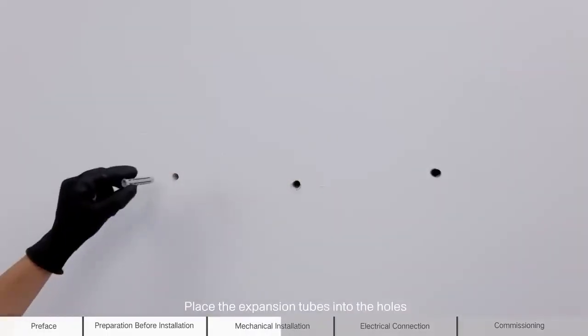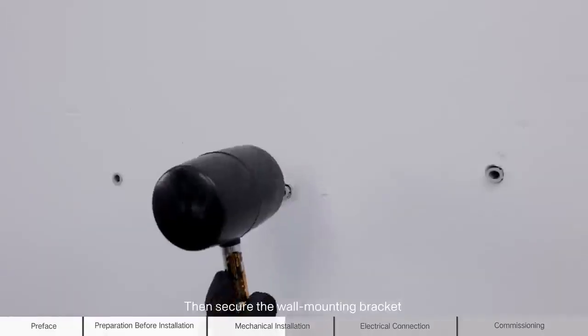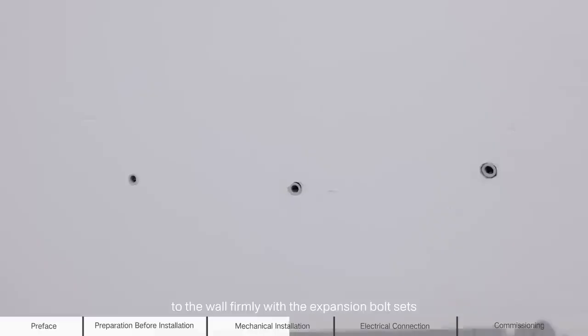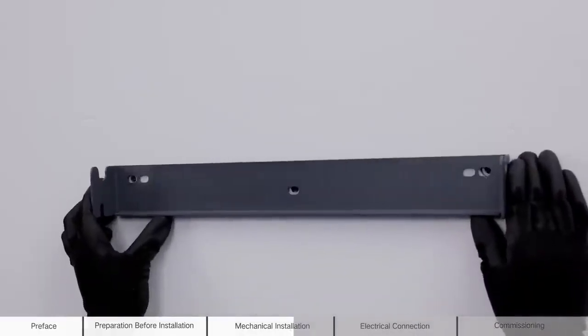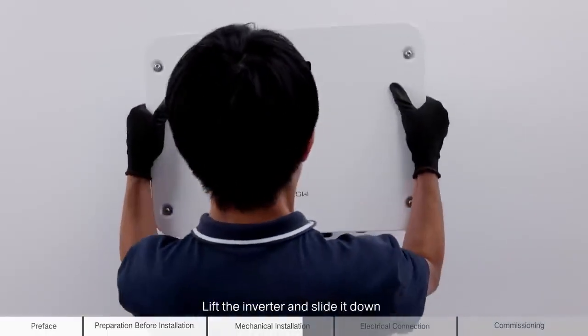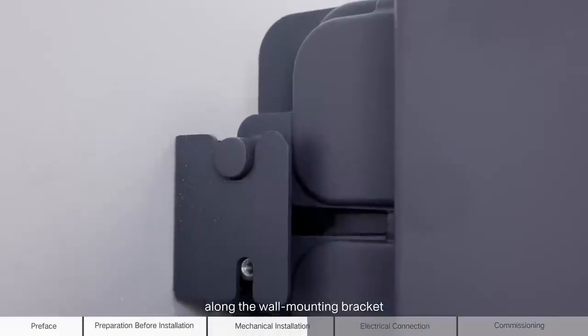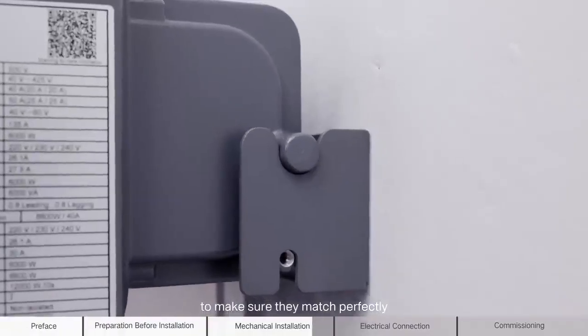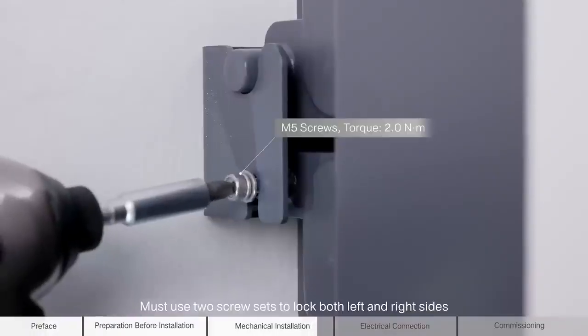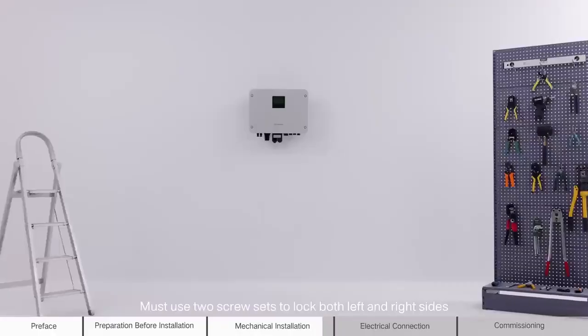Place the expansion tubes into the holes. Then secure the wall mounting bracket to the wall firmly with the expansion bolt sets. Lift the inverter and slide it down along the wall mounting bracket to make sure they match perfectly. Must use 2 screw sets to lock both left and right sides.